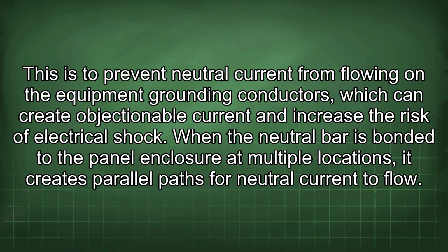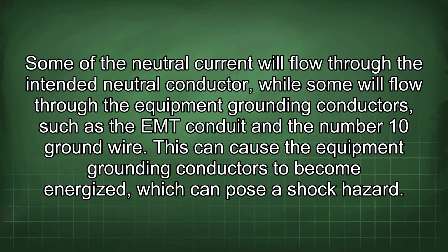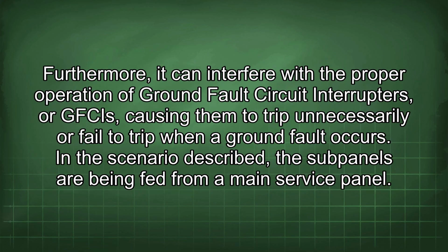When the neutral bar is bonded to the panel enclosure at multiple locations, it creates parallel paths for neutral current to flow. Some of the neutral current will flow through the intended neutral conductor, while some will flow through the equipment grounding conductors such as the EMT conduit and the number 10 ground wire. This can cause the equipment grounding conductors to become energized, which can pose a shock hazard. Furthermore, it can interfere with the proper operation of ground fault circuit interrupters, or GFCIs, causing them to trip unnecessarily or fail to trip when a ground fault occurs.